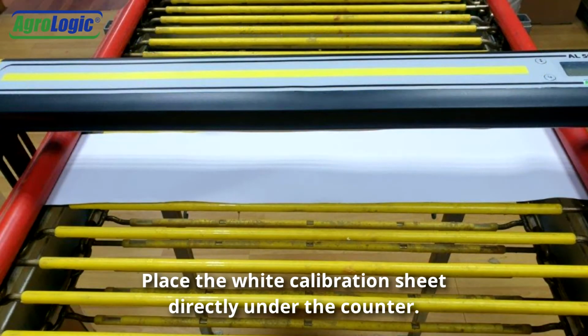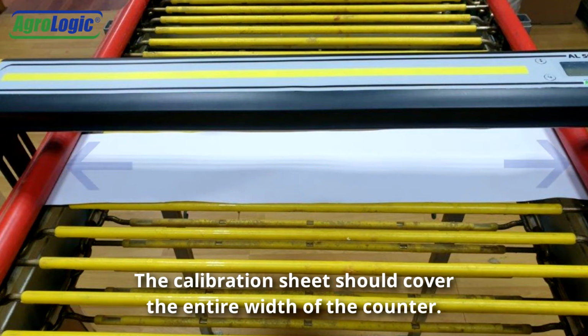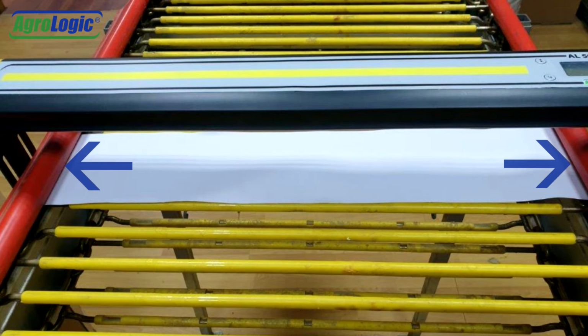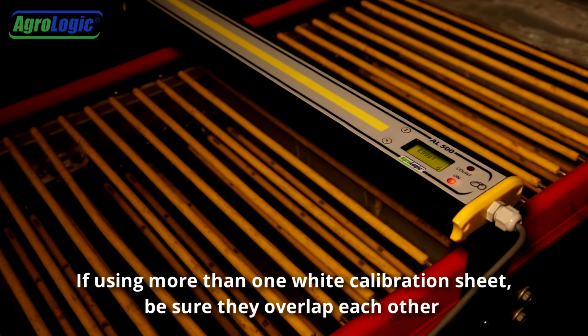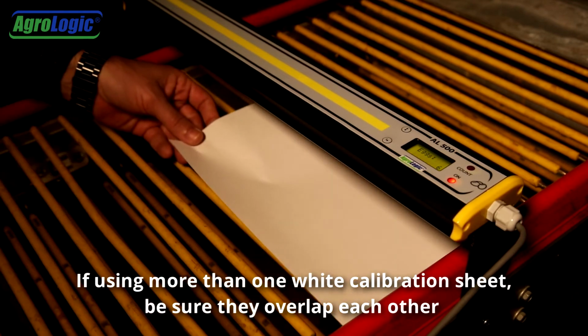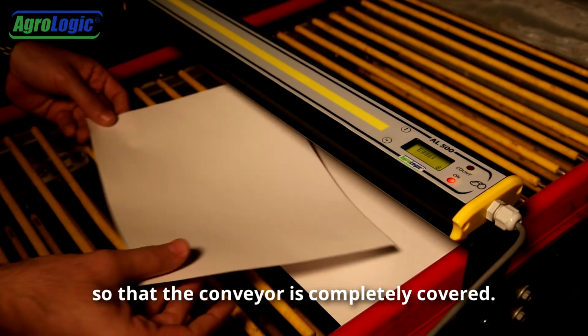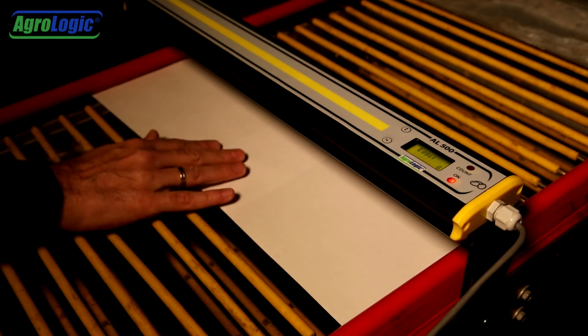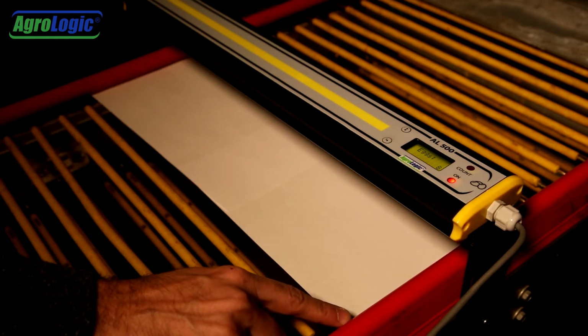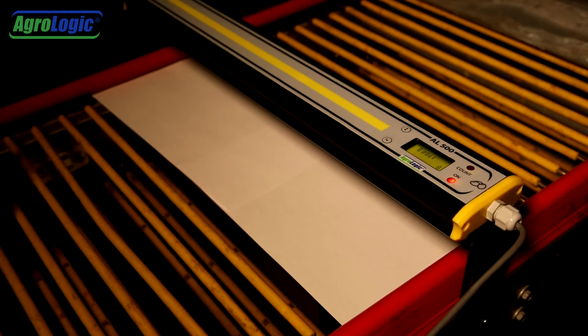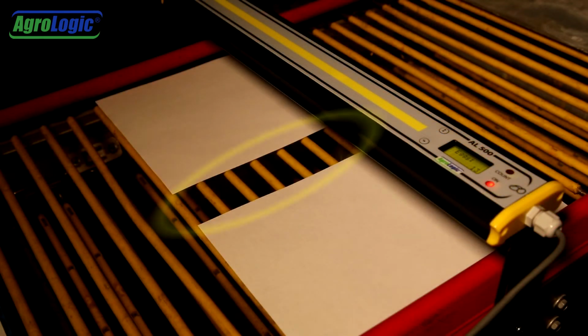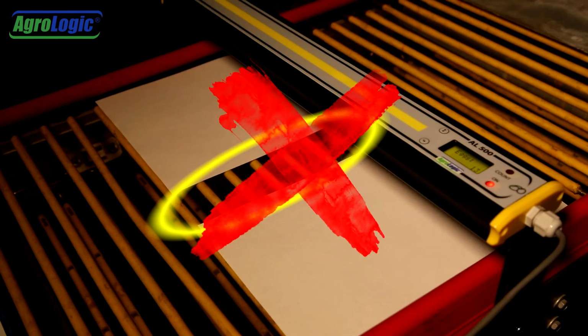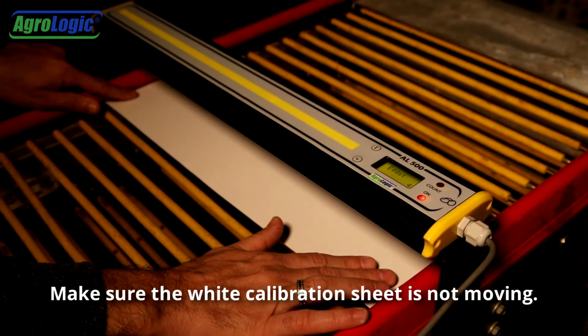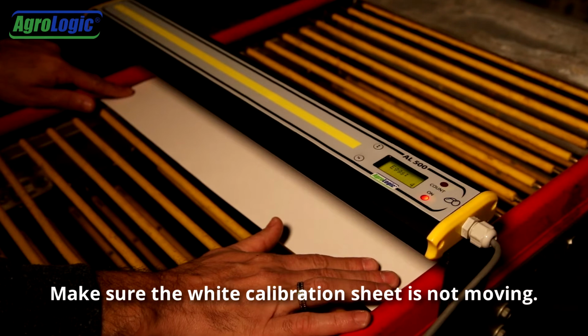Place the white calibration sheet directly under the counter. The calibration sheet should cover the entire width of the counter. If using more than one white calibration sheet, be sure they overlap each other so that the conveyor is completely covered. Make sure the white calibration sheet is not moving.